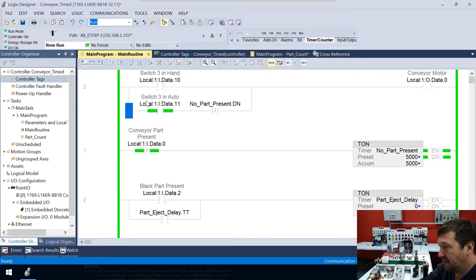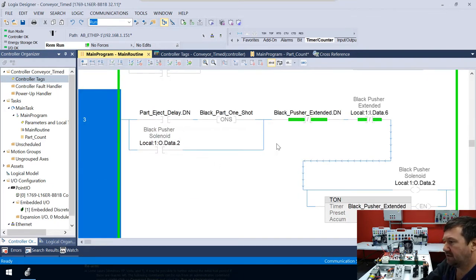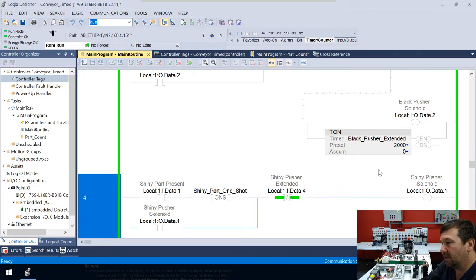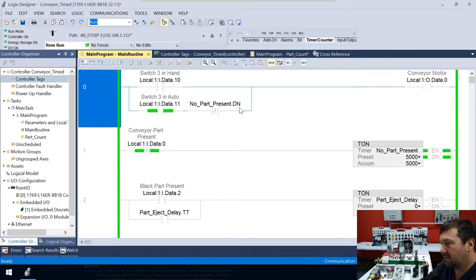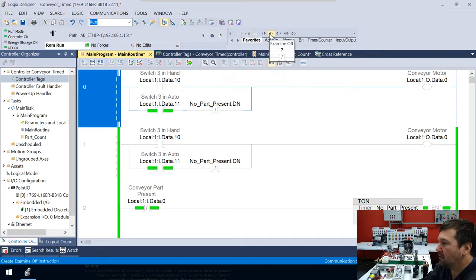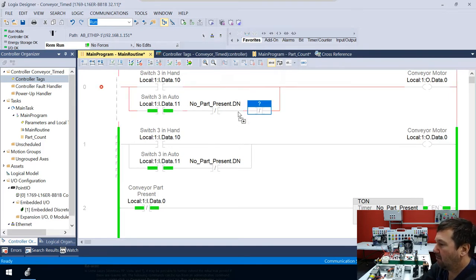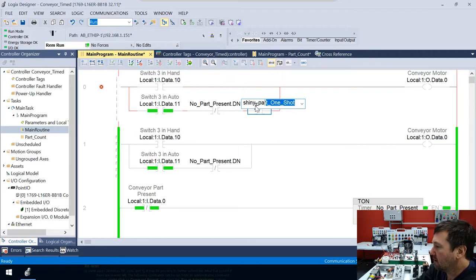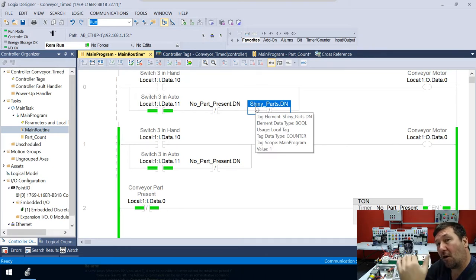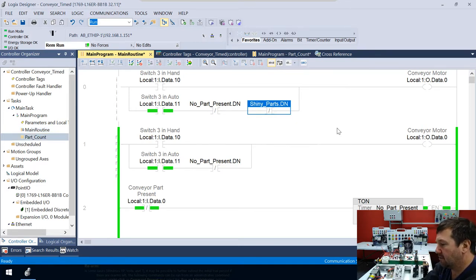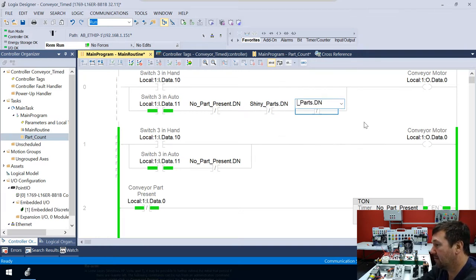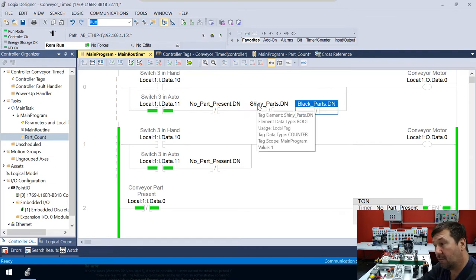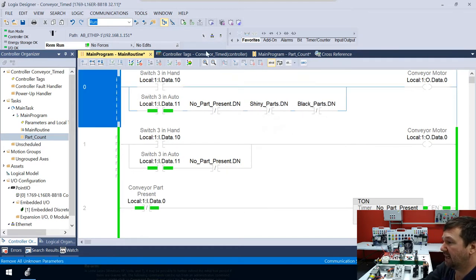And so we see here, here's our auto run. Now earlier on, we added our interlock that we wanted to stop it right beside of the output. In this case, we only want to do it in auto mode. So we're just going to put them down in this branch. So we're going to edit this rung. And we're going to go to our favorites tab and go for an examine if off. And we're going to examine off shiny parts dot dn. Because we want to run as long as that dot dn bit is not made, or our accumulated value is not greater than or equal to our preset. Now let's highlight that and you can just hit control C and then control V. That's going to put another one in. But instead of the shiny parts, we now want the black parts. So now if we're full of shiny parts or we're full of black parts, we want to stop. So let's put that in.